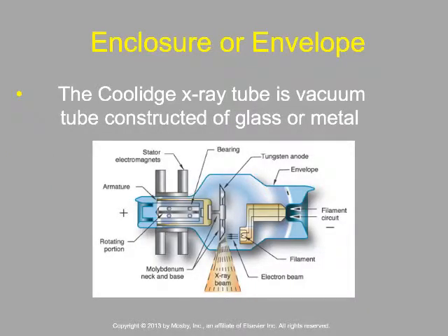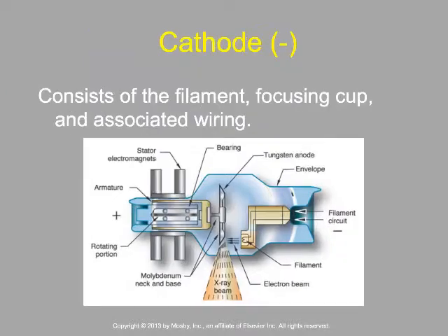The Coolidge x-ray tube has a vacuum generally constructed out of glass, housed within a glass envelope — think of it like a light bulb. On the cathode side, that consists of the filament, the focusing cup, and associated wiring from the step-down transformer. The step-down transformer powers that cathode to begin thermionic emission, which starts to produce heat, boiling off electrons and producing a space charge effect.